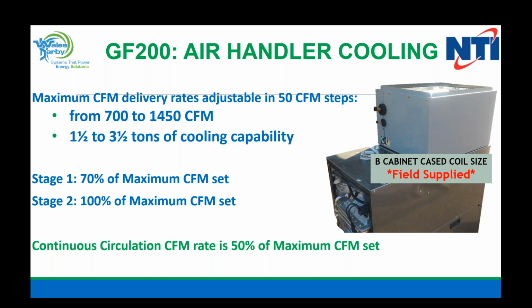We have a couple of condo complexes going in right now with GF200s, and we're actually doing 2 zones, 1 zone upstairs, 1 zone downstairs, with a 2-stage outdoor compressor, and we're tying it in with a zoning system, and they're working out extremely well. One has a mechanical room in the basement that it's in, and on the other job site, they spray foamed the ceiling and the roof, and the GF200 is actually in the attic.